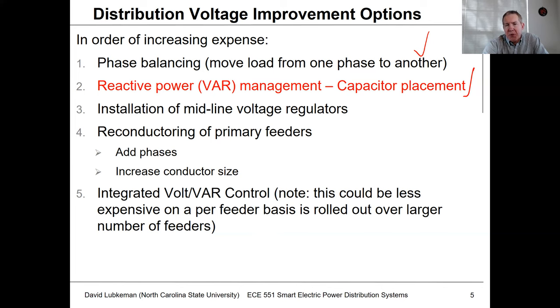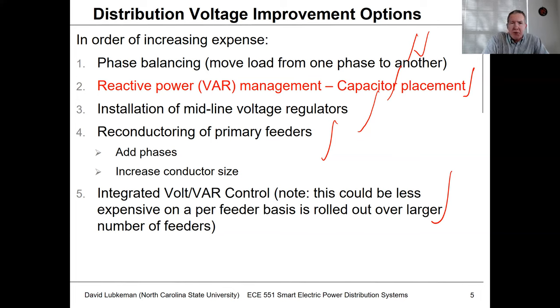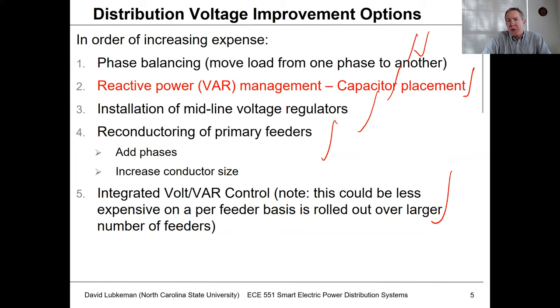If rebalancing or capacitor placement can't fix the issues, you look at voltage regulator placement, which we discussed previously. If that still doesn't fix everything, you put in larger conductors or upgrade from single-phase to two-phase or three-phase, which gets very expensive. The fifth option is integrated volt-VAR control, coordinating all capacitor banks and line regulators on a circuit — most expensive due to communications and computer system overhead, but cost-effective when implemented utility-wide.